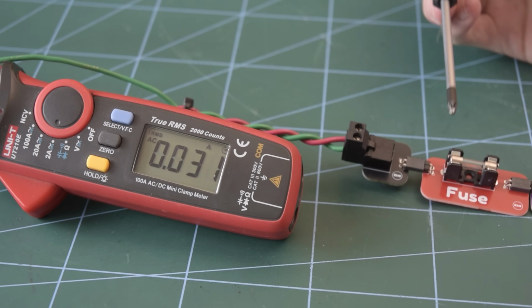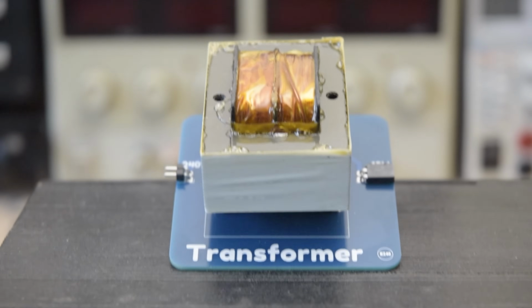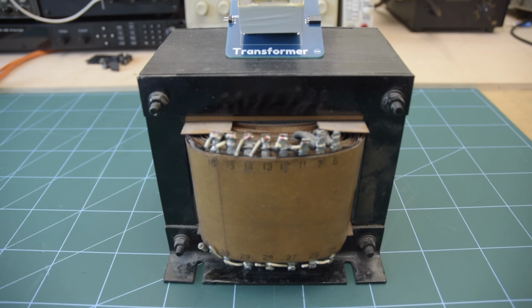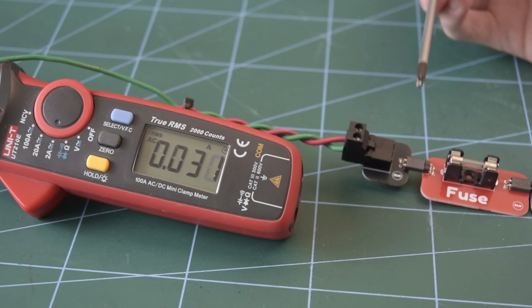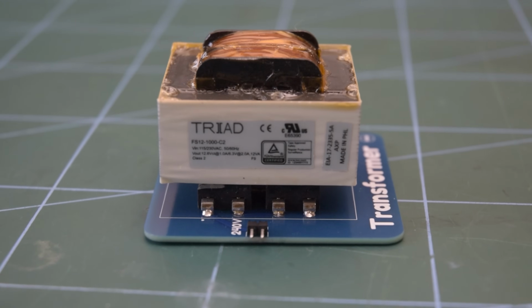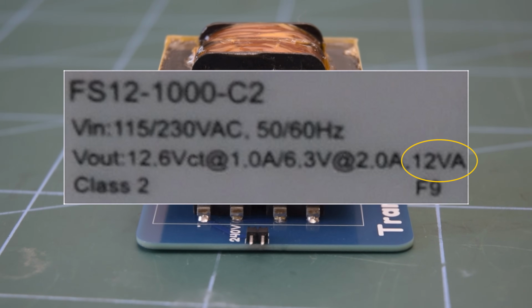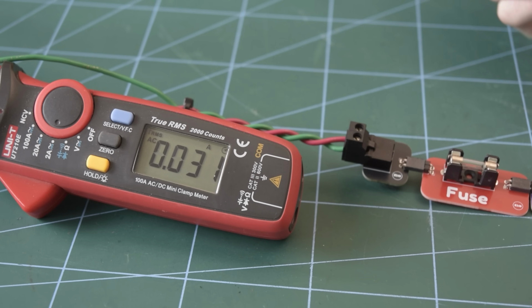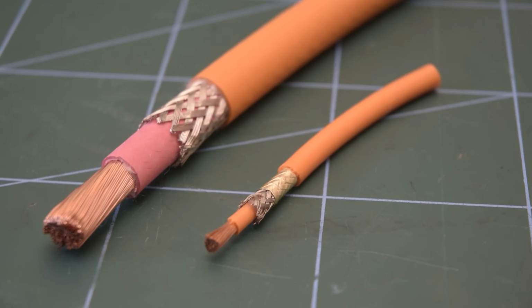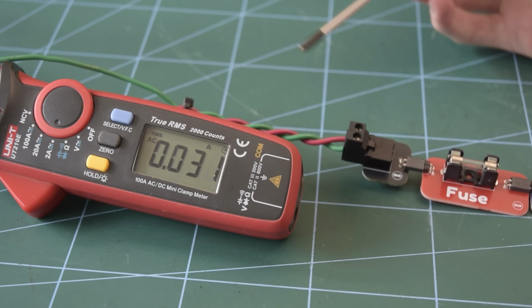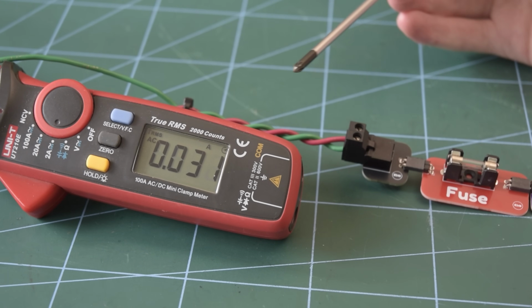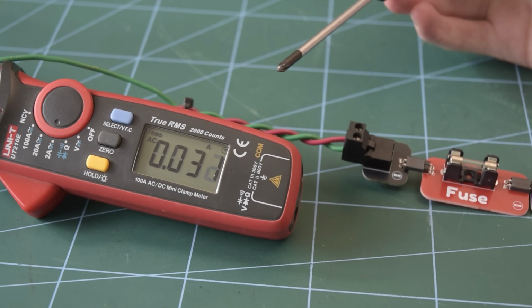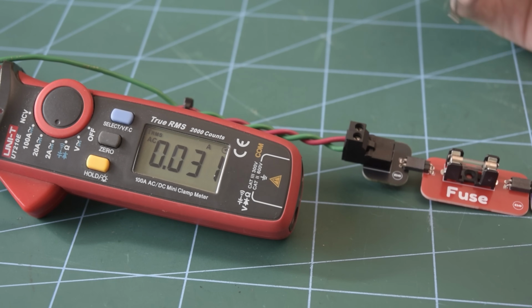Apparent power is what dictates the sizing for all components in the national grid. If you look at any transformer, the power it can handle won't be real power in watts, it'll be apparent power in VA—as you can see on this transformer we're using, which is rated for 12 VA, or volt-amps. This is simply because the cable and the thickness of windings in transformers are dictated by the current, not the power. So even though this current isn't actually doing anything, just going in and out of the loads, we still have to size all our cables and switchgear and other stuff for this apparent power.